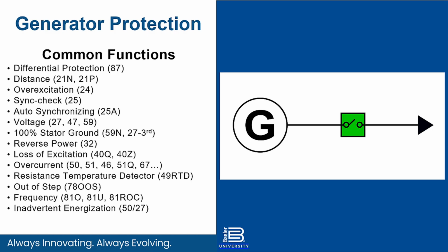So for generator protection, some of the more advanced functions, in addition to the common ones that we've seen before, you might be using a distance function, whether that's phase or neutral. Differential protection, again with the 87, is very common on a generator protection application.